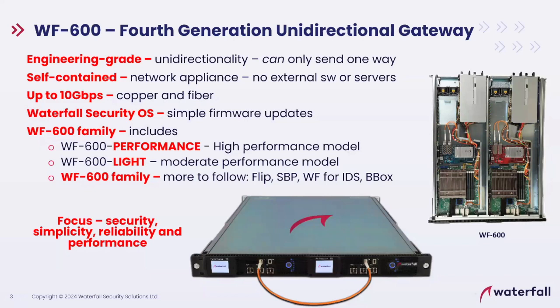In the rack mount version, if we lift the lid and look under the hood, we still see the physical divider down the center of the unit. An auditor can run their fingers down that divider and verify that there is no cross connect inside the unit. Separate hot swap power supplies on each side, separate CPUs, separate everything. The only connection between the left and right sides of the unit is on the front panel: the fiber optic cable, the fiber optic transmitter on one side, the fiber optic receiver and the logic on the other side.